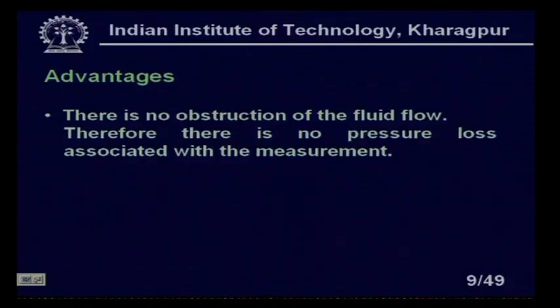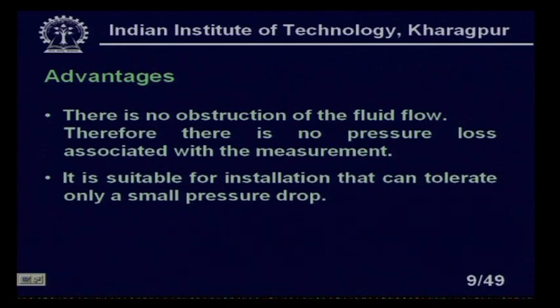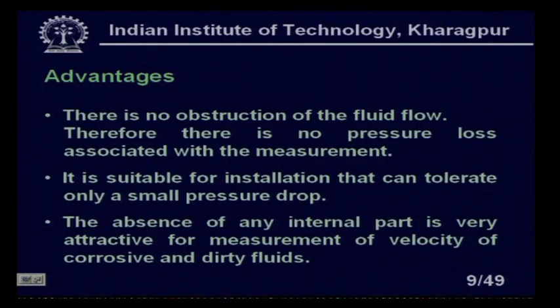There are several advantages of this type of flow meter. First, there is no obstruction of the fluid flow, therefore there is no pressure loss associated with the measurement. It is suitable for installations that can tolerate only a small pressure drop. The absence of any internal parts is very attractive for measurements of velocity of corrosive and dirty fluids, unlike turbine flow meters or orifice meters where internal components must be installed.